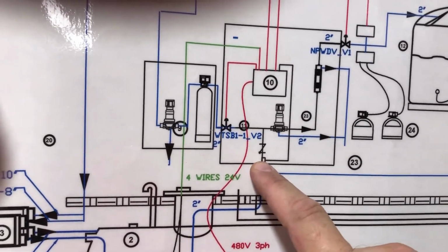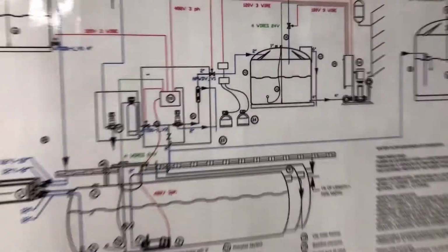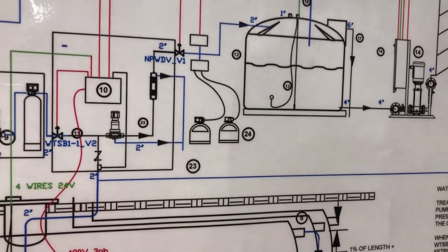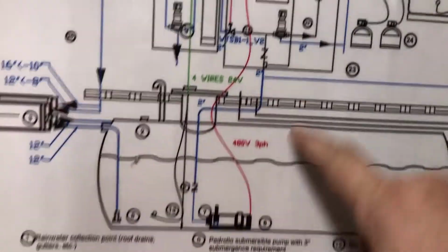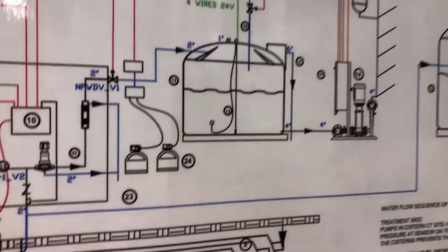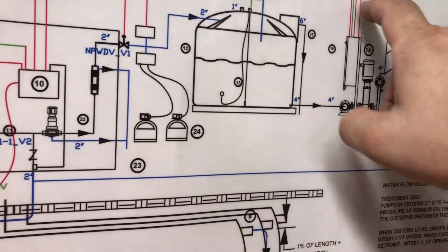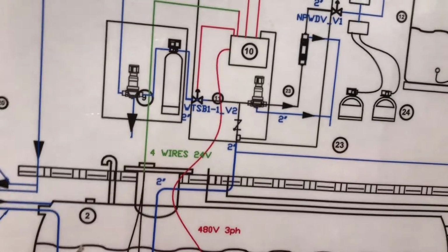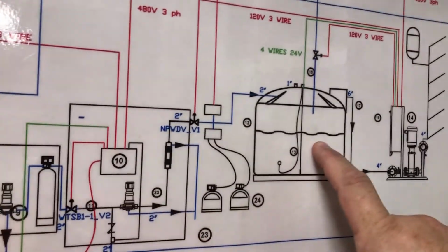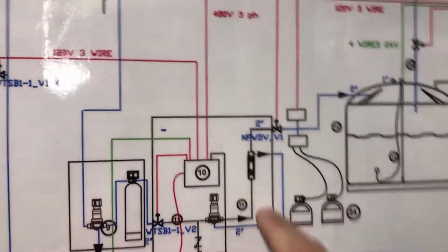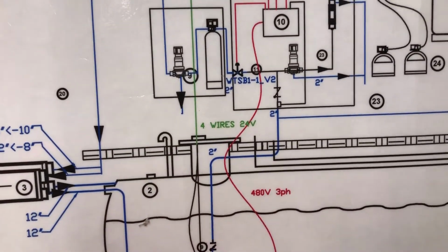The pumps are actually controlled based on pressure. There's a pressure transducer here, which you can see right there. Because we're filling two different day tanks, we don't look at the day tank levels to start this pump. We look at pressure here. These two control panels actually open valves back here, and over here there's a float valve for the irrigation one. When this tank needs water, this controller, that's this controller right here, opens this valve, the pressure drops, the pressure sensor here detects that, and the pumps come on.